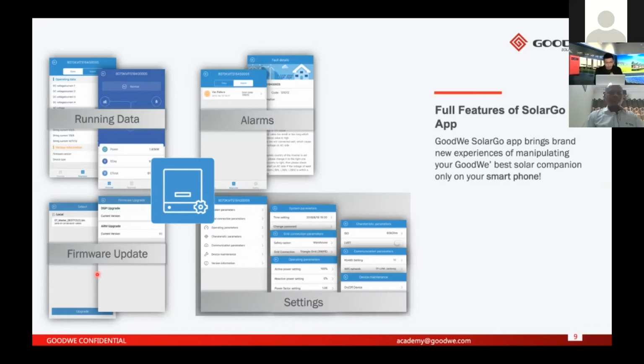The last part is the settings. Settings are basically about the advanced functions we offer based on our inverters. For example, you can set the PF value. You can choose to let the inverter output certain reactive power based on your demand. Also, if you use a third-party data logger, here you can set the RS485 port and the Modbus address, based on the requirements of third-party data loggers like SolarLog and some other brands.